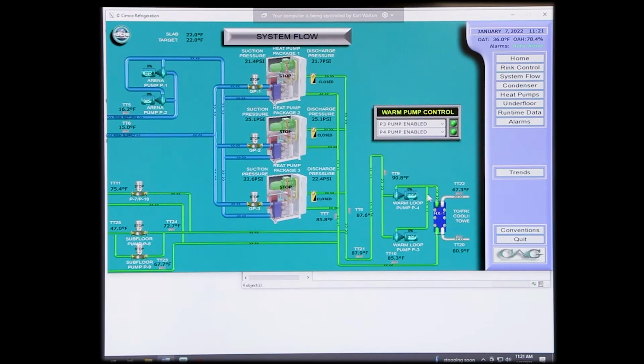Over here you have your P3, P4 pumps. Again, remember, as I said before, on different screens you have the ability, if you have a problem with a pump or you need to shut something off, to tell the computer don't run it. Before you would go downstairs and turn a hand-off-auto switch off, you have to tell the computer, I don't want you to run. Otherwise you will get an alarm. Instantly it tries to start that. It will generate one. So again, P3, P4, these are your warm loop pumps here. For the warm glycol loop, you could highlight one of those and enable or disable. They should always be enabled because we flip-flop them on each other's start.